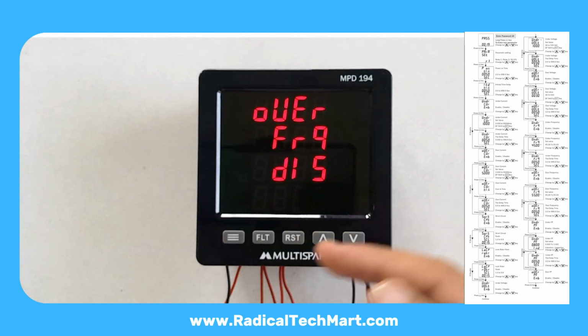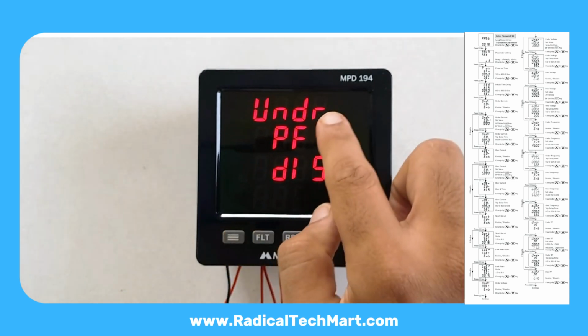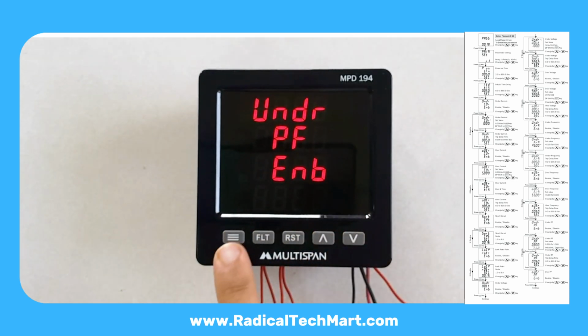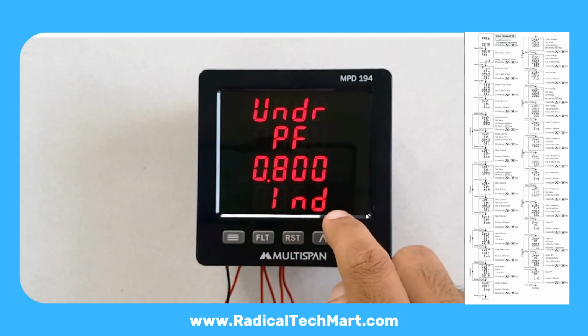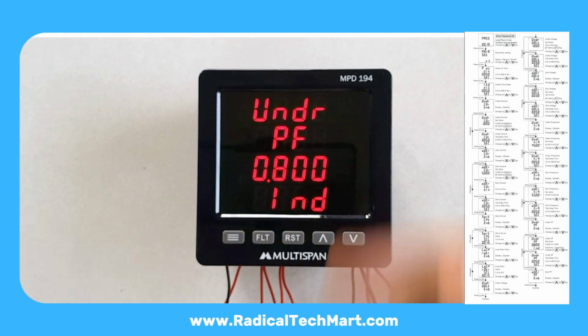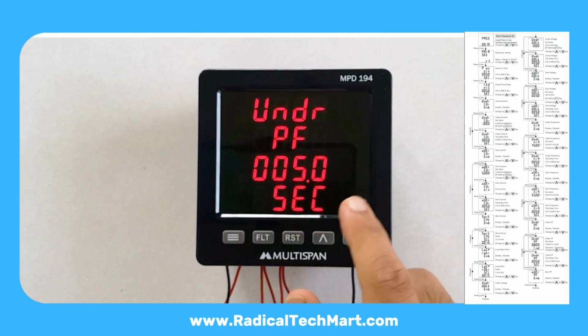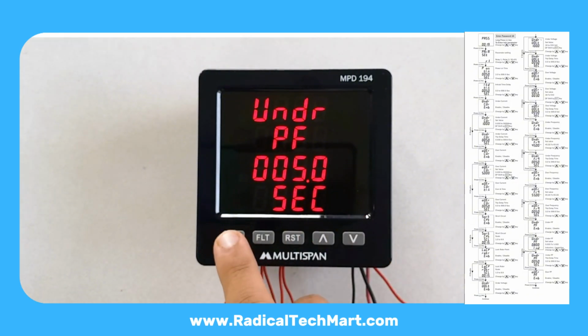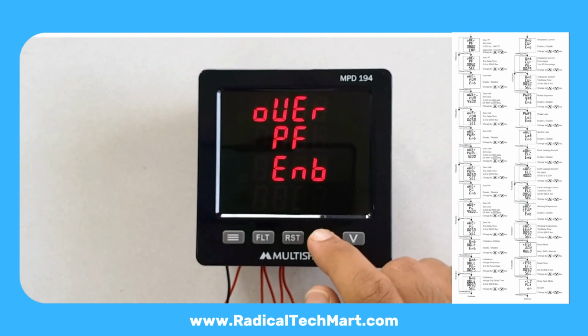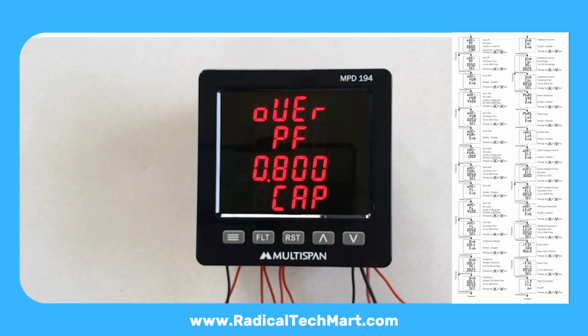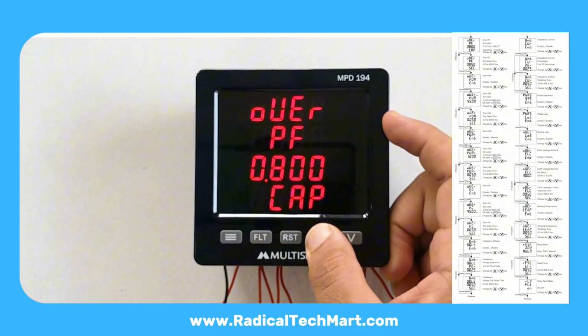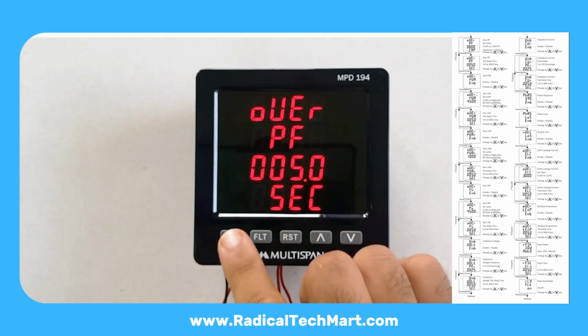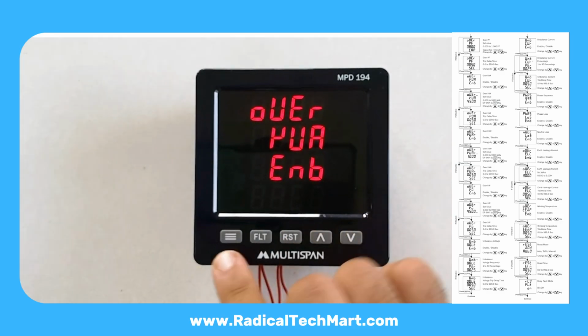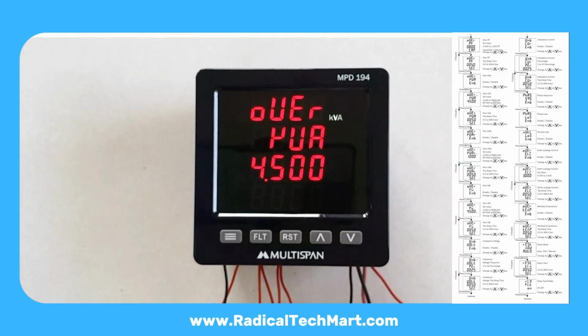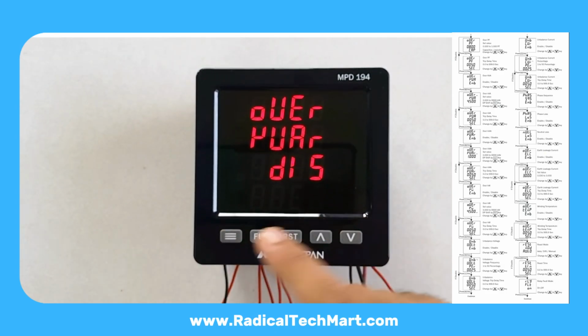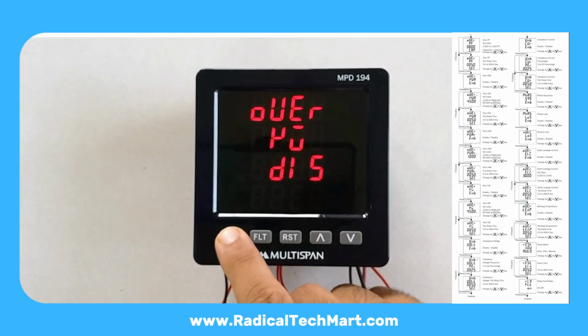Press Set. You also get under power factor, under PF. Enable, disable. Set PF value, default 0.8 lagging. If PF goes below this, it will trip after the set delay. Over PF, for capacitive PF going beyond a set limit, example 0.8 lead. Over kVA, over kVAR, over kW. Enable, disable. Set thresholds for each if you want power-based tripping.